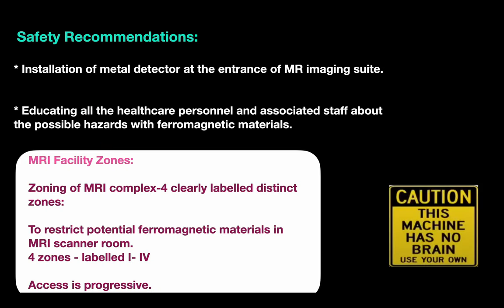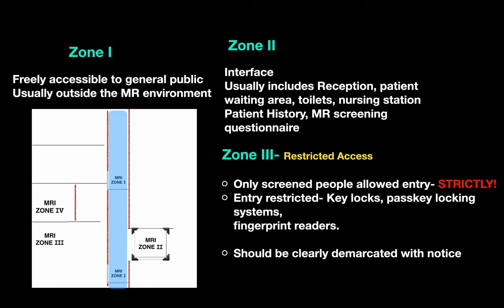Safety recommendations include installation of metal detectors at the entrance of the MRI imaging suite and educating all healthcare personnel and associated staff about possible hazards with ferromagnetic materials. For this reason, the MRI complex is divided into four clearly labeled distinct zones to restrict potential ferromagnetic materials from entering the MRI scanner room, with progressively restricted access.